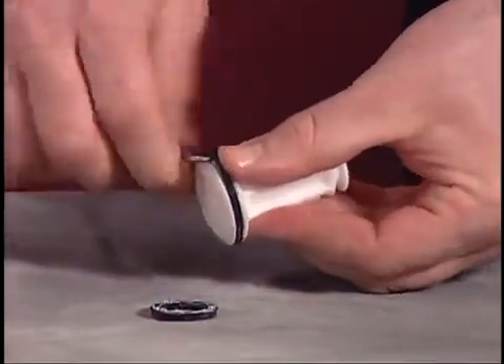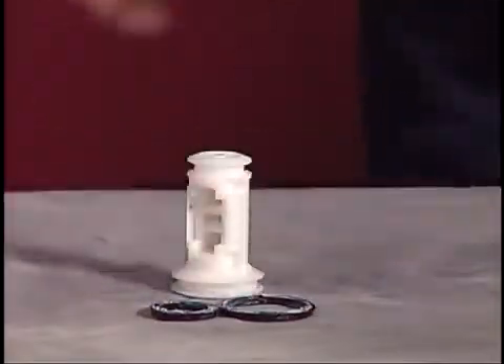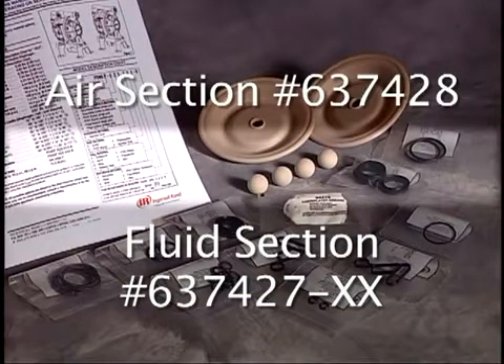This completes disassembly of the pump. Clean all components prior to reassembly. Use ARO service kits when repairing this pump. Apply Lubriplate FML-2 grease to the O-rings and U-cups prior to reassembly. A packet of grease is supplied in both service kits.